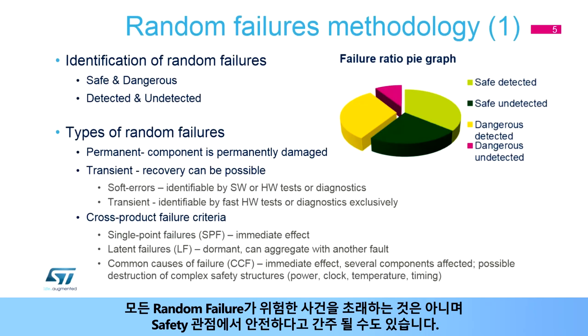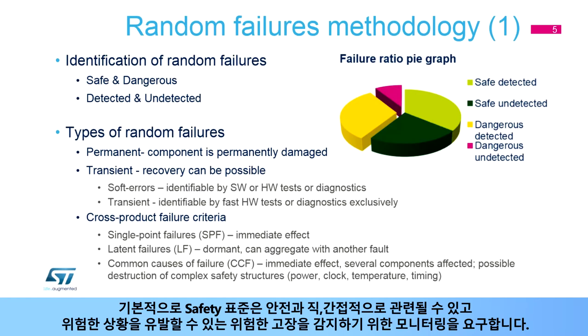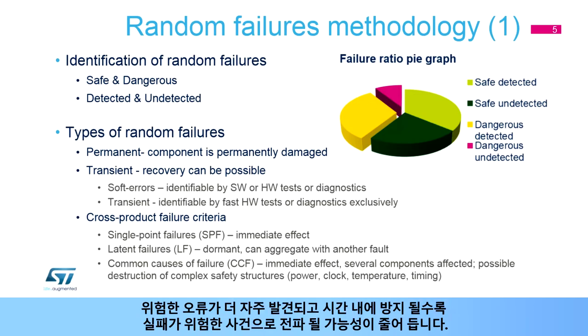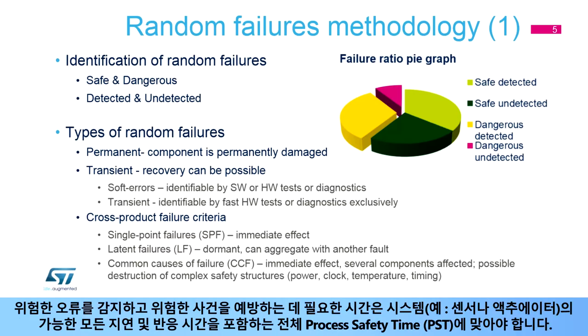Not all random failures result in a hazardous event, and they may even be considered safe from a safety point of view. Safety standards require monitoring to detect dangerous failures that may be directly or indirectly related to safety and have the potential to cause a dangerous situation. Both safe and dangerous errors can either be detected or stay hidden and undetected by the system. The time needed to detect dangerous errors and prevent hazardous events must fit into the overall process safety time, PST, which includes all the possible delays and reaction times for the system, for example, on sensors or actuators.